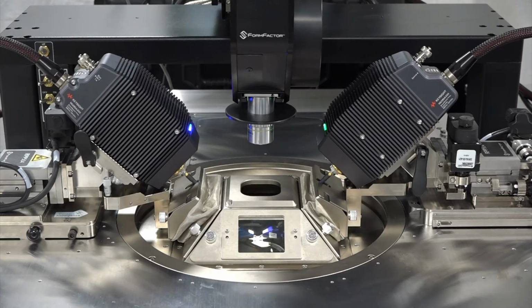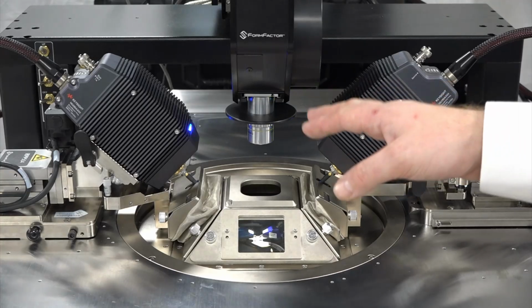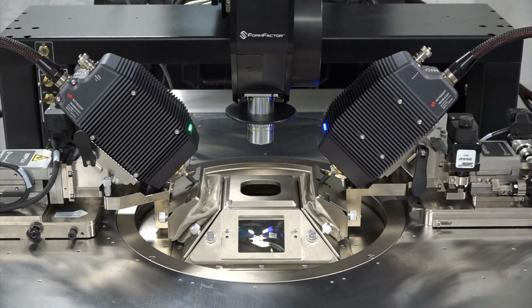So what I'm just doing at the moment is I've moved to the contact height that I had set beforehand. Contact height, you have to be quite careful, certainly on a Summit 200, because the movement range is very large. Currently my contact height is set to 42 millimeters. So you want to make sure that it is in the right general range, that there's going to be nothing unexpected. And I had my microscope set up for that height previously, so I'm happy to do that. But be very careful if you've come to a machine totally cold.